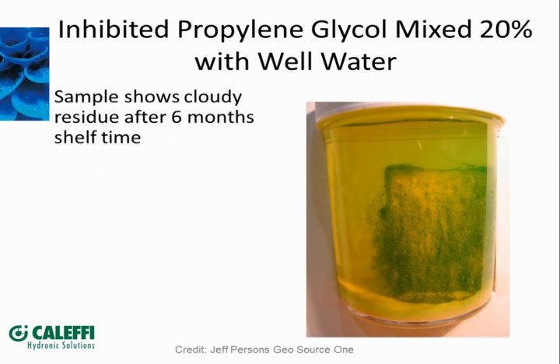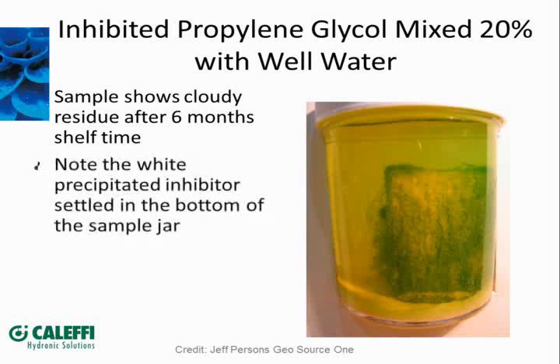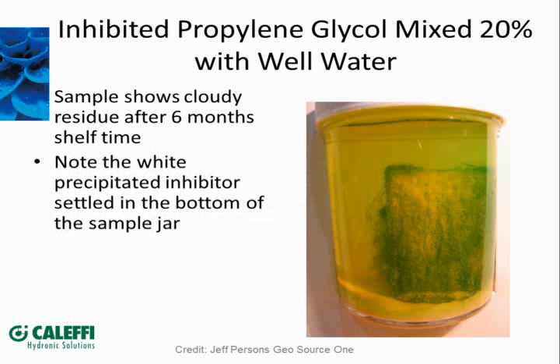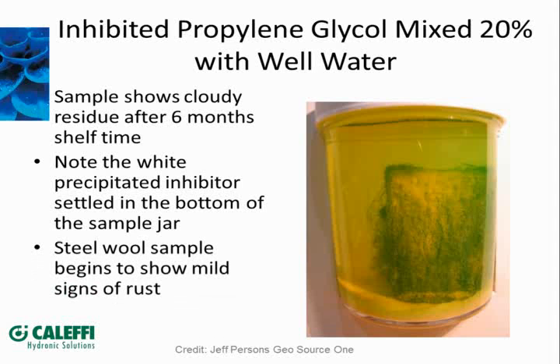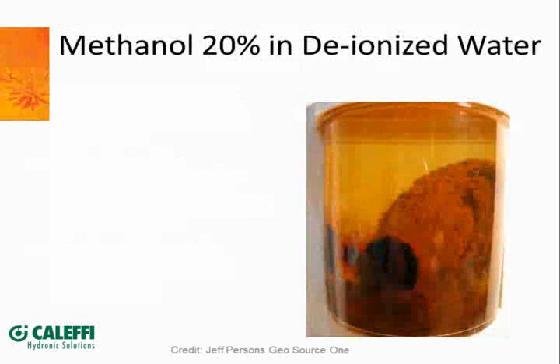Here's a similar sample of propylene glycol, again 20% mixed with well water. In this solution you'll notice a heavy layer of sediment at the bottom of the container, and some white sediment on the steel wool sample, which is starting to show signs of rust and corrosion. What's happened is the mineral content in the well water has complexed with inhibitors in the antifreeze, causing those inhibitors to precipitate from solution and rendering the propylene glycol a corrosive solution—no longer protecting the metals in the system from corrosion.